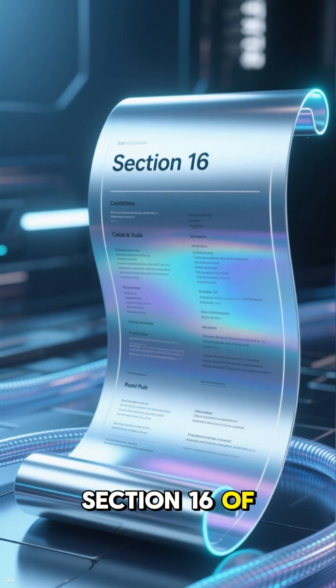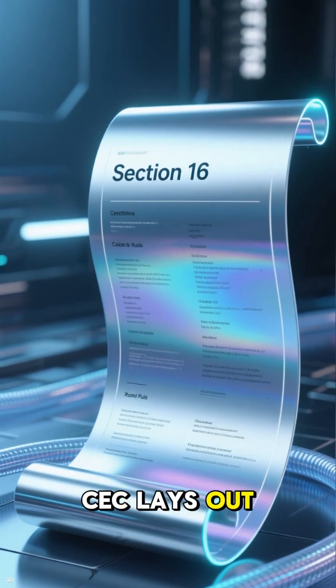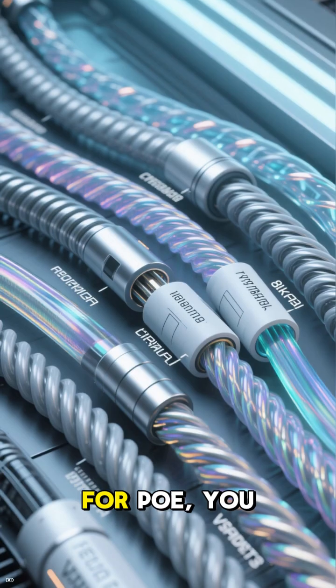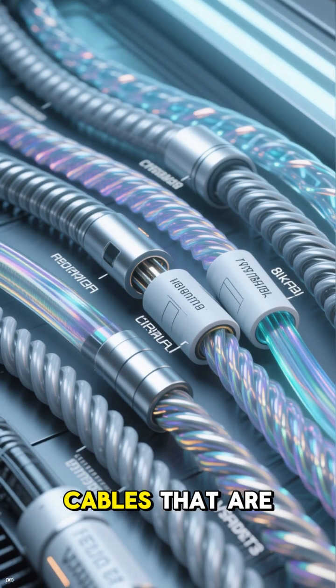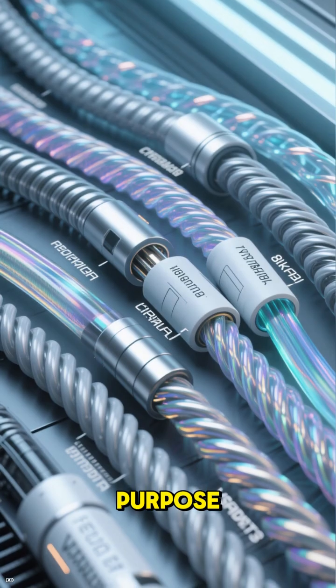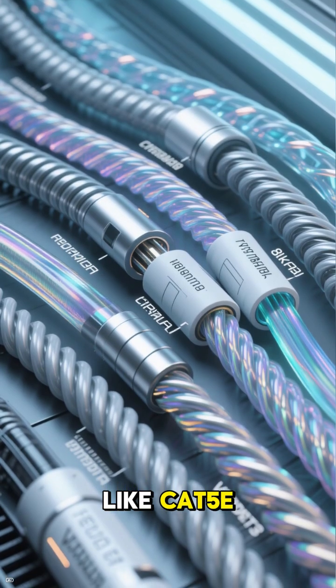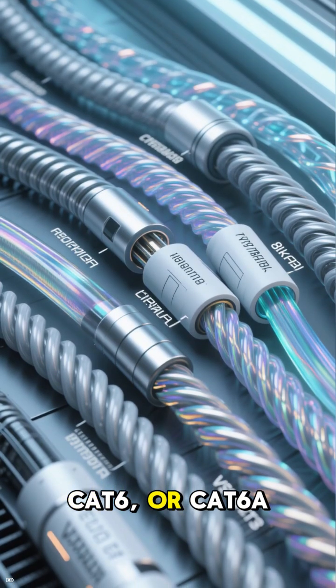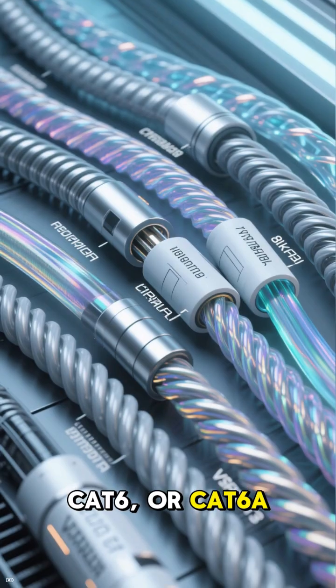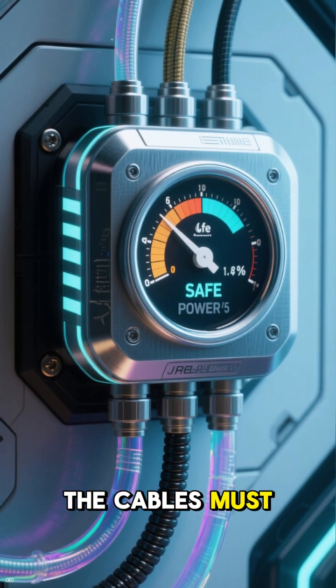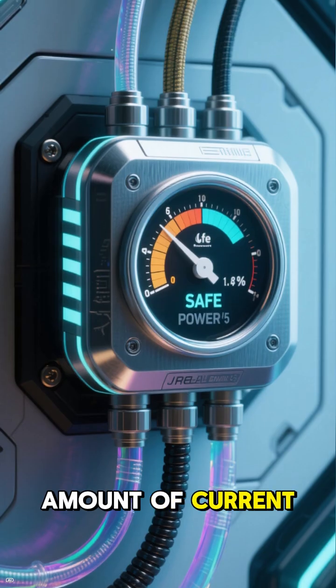So, what about the cables themselves? Section 16 of the CEC lays out the rules. For PoE, you need to use twisted pair communication cables that are specifically listed for this purpose, like Cat5e, Cat6, or Cat6A. The code is very clear. The cables must be suitable for the amount of current they will be carrying.